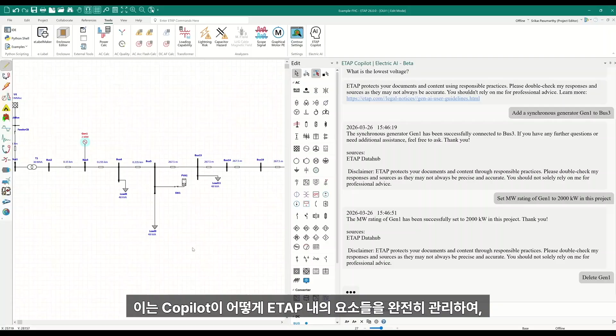Since ETAP requires values in kilowatt, Copilot automatically converts and updates the generator with a 2 megawatt rating. This process doesn't stop at adding or modifying elements. Copilot can also delete elements from the one-line diagram. By simply asking it to delete Gen 1, Copilot removes the generator entirely from the system. This demonstrates how Copilot can fully manage elements in ETAP, adding, configuring, and deleting them without manual intervention.